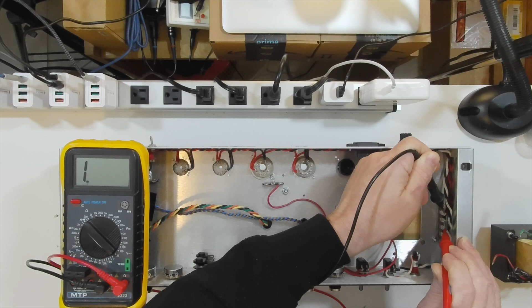The next thing to do is just check that you don't have any shorts anywhere. So I've got my ohm meter set up here. It's on 200 ohms. You could also use the beep test if you want, and that's an easy way to not have to just look up and see if everything's working. If you hear the beep, you know that you've got your continuity. So the first thing that I checked was the connections going to the heater string, the red and black wires, which is also where the green wires had connected from the transformer. And what you want to do is test between those two and make sure you don't get a beep. There should be no connection between the red and black wire. That would be a short, and we don't have one. We're good here. The reason you can't test that when the transformer's connected is it would essentially show up as a short. So you couldn't have checked that with the transformer in place. It wouldn't have really told you anything. I've checked the black and red.